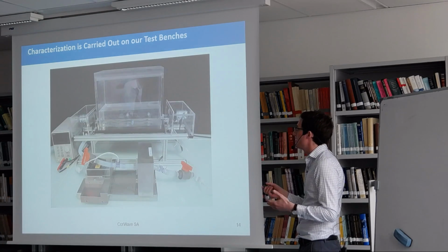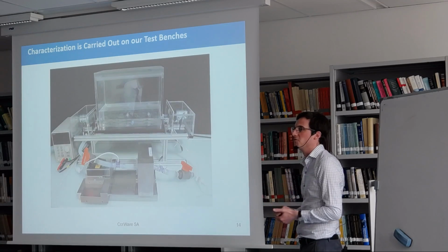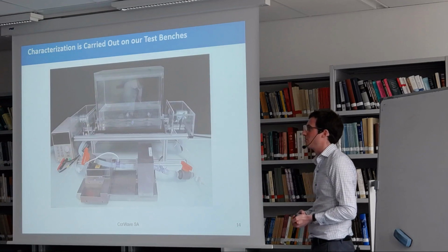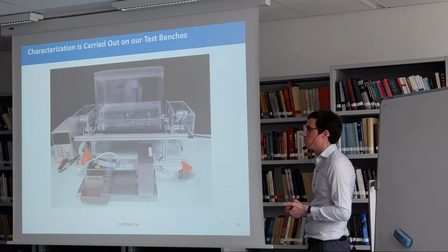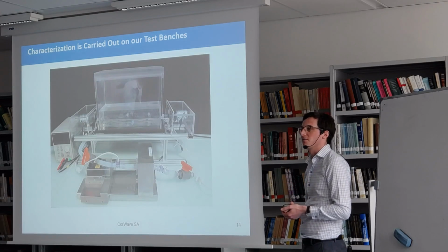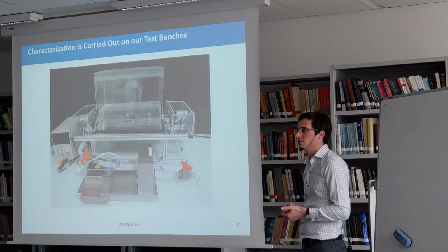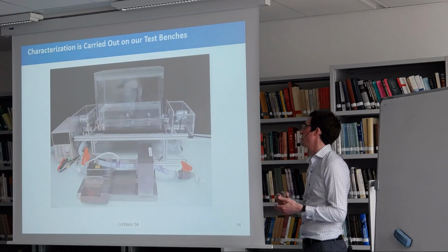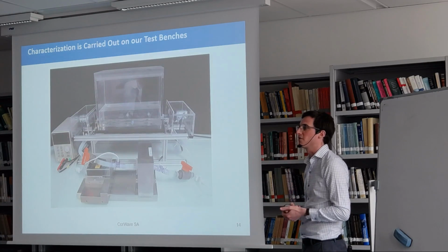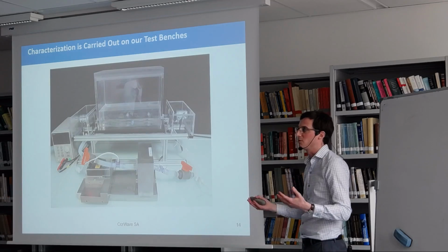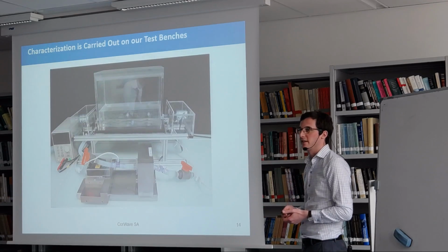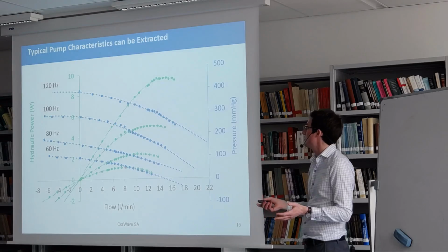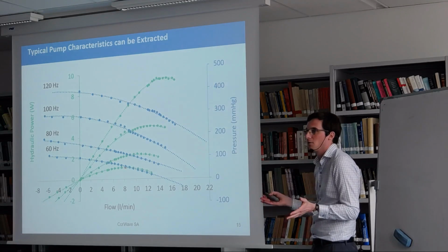We have pressure sensors, flow sensors, and temperature sensors included, and we can control the temperature. We measure the displacement of the membrane through a laser, and we measure the electrical consumption. With all this data we can measure the hydraulic output, the efficiency, and all that, and in the end it allows us to extract classical pump curves.